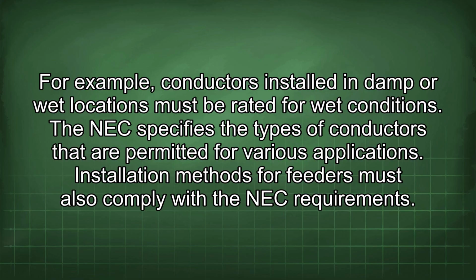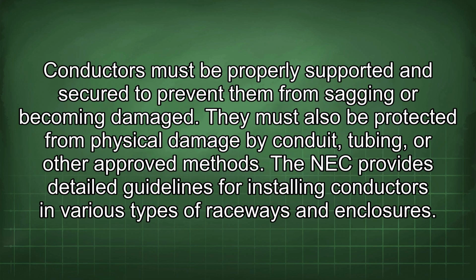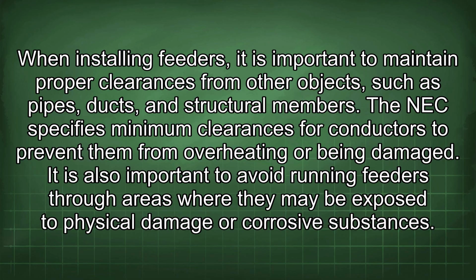Installation methods for feeders must also comply with the NEC requirements. Conductors must be properly supported and secured to prevent them from sagging or becoming damaged. They must also be protected from physical damage by conduit, tubing, or other approved methods. The NEC provides detailed guidelines for installing conductors in various types of raceways and enclosures. When installing feeders, it is important to maintain proper clearances from other objects such as pipes, ducts, and structural members. The NEC specifies minimum clearances for conductors to prevent them from overheating or being damaged.